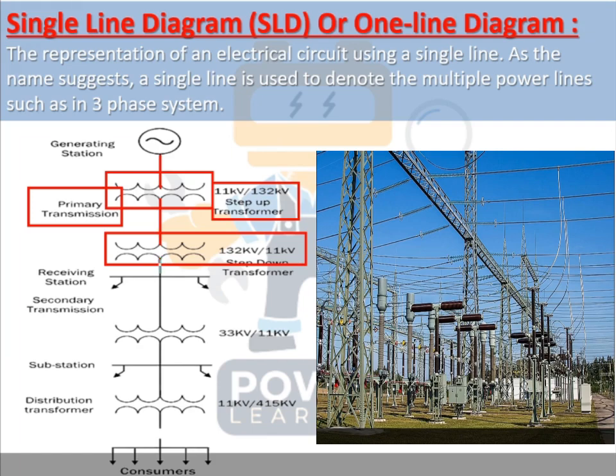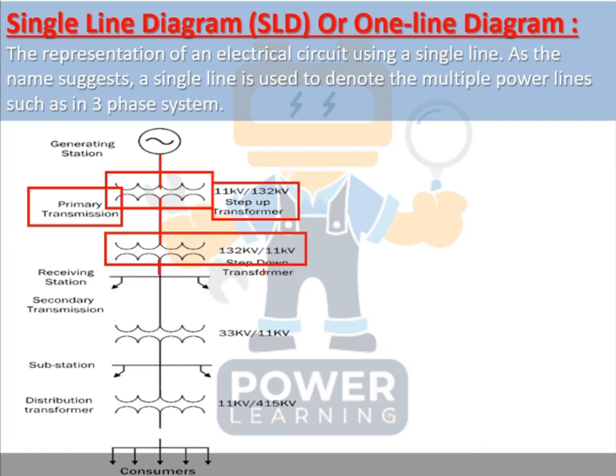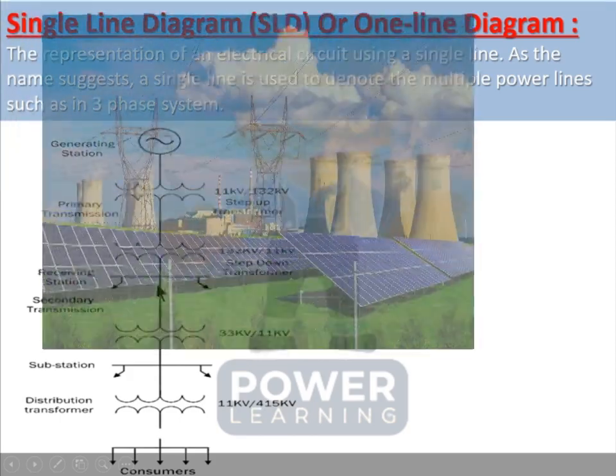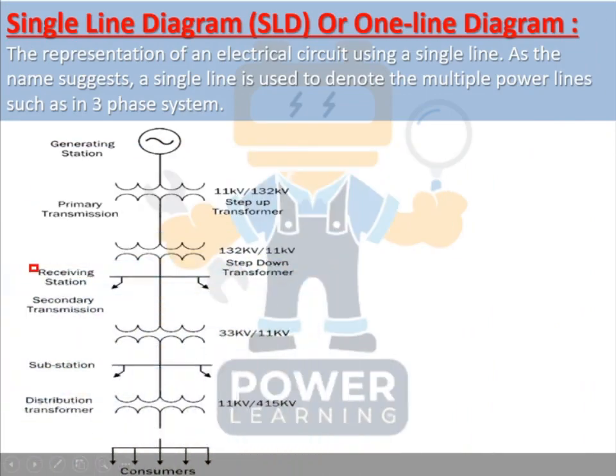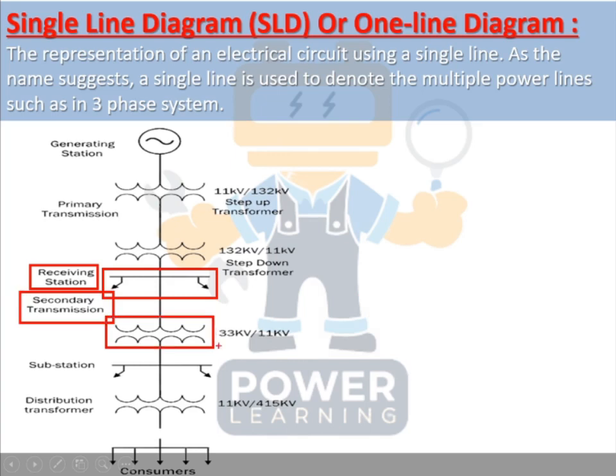The line from the step-down transformer connects to a receiving station, which is a separate part. This transformer steps down 132 kV to 11 kV, and the stepped-down power is received at the receiving station. You can explain this easily to another engineer using single line diagrams with standard symbols.